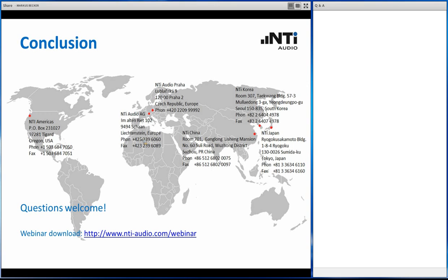What is important, again, is that the license will be installed on the XL2 instrument. So the data transfer is enabled by this license. Secondly, you can install as many Data Explorer software copies on any PC you like. You can even install the Data Explorer without a license, and then you can run it in a demo mode to get a feeling for that software. That is, I think, the most important stuff to be said about licenses.